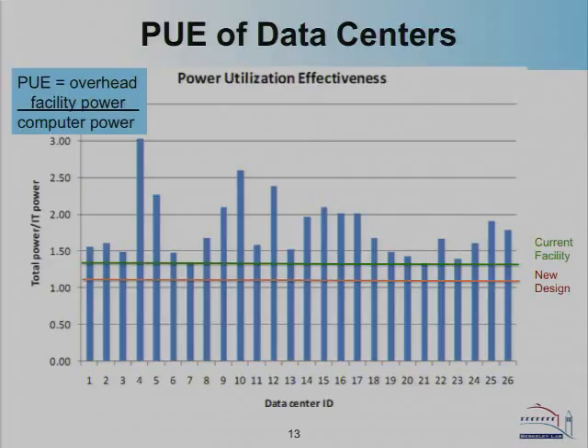So everything you lose from the transfer of energy—power throughout the machine room floor, through UPS devices, loss in cooling, the energy it takes to run the cooling devices, which can be substantial—is all in that number above one. This is where the NERSC facility sits, at about 1.3.